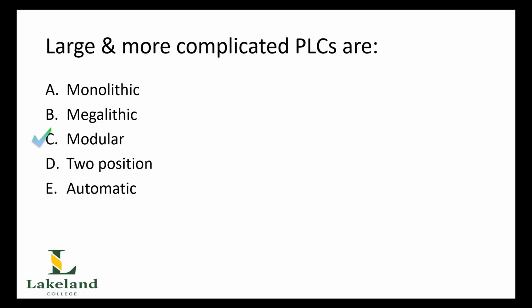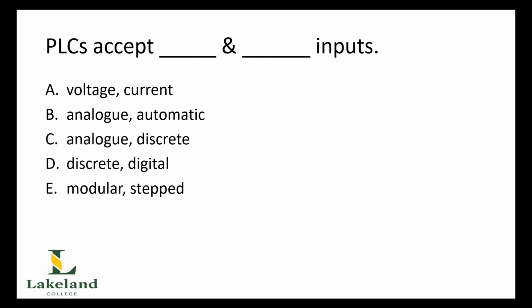The modular PLC is the larger ones, the ones that we are able to add input-output modules to or take away input-output modules from. We're even able to change the ladder logic or the sequencing logic of them. These are the big ones that can be reconfigured. The monolithic ones, these are the ones for things like packaged pieces of equipment that we are not able to alter.